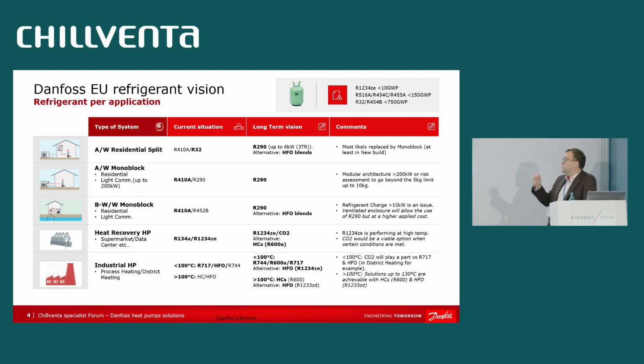Our main development in this field has been to maximize efficiency and reduce as much as possible the refrigerant charge, both on the compressor and heat exchanger side, in order to remain below 5 kilograms of propane per circuit. This means you can build a heat pump up to 200 kilowatts with two circuits, each below 5 kilograms.